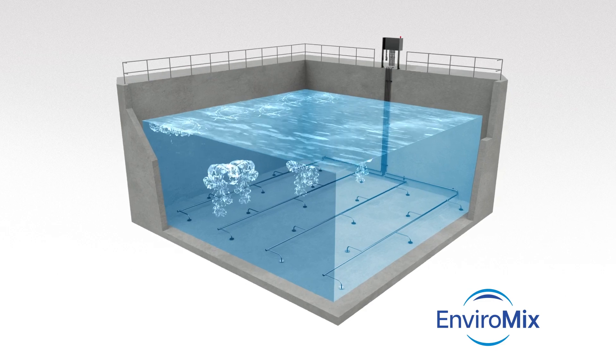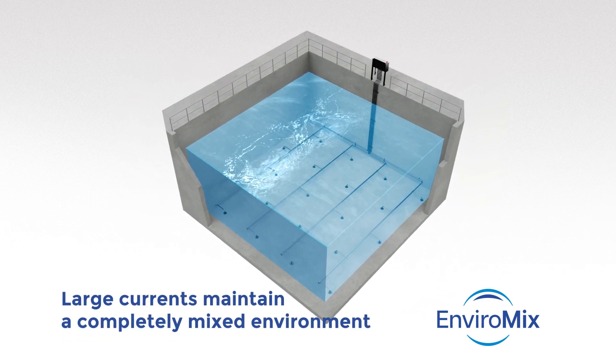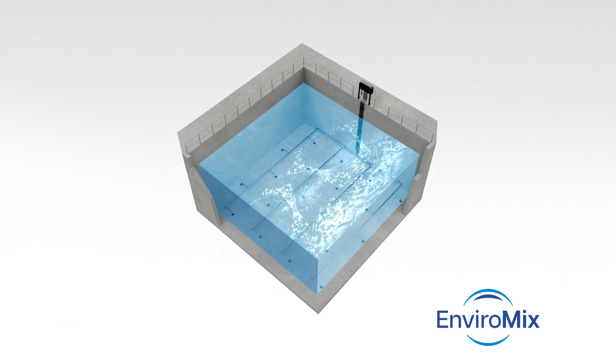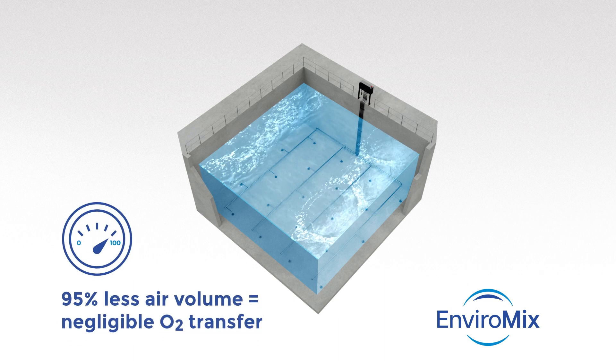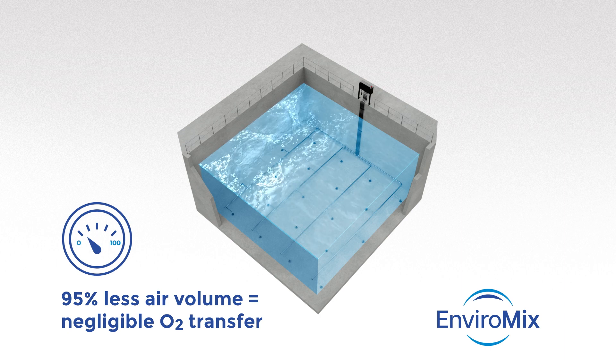On the surface, you can see the convergence of these currents and the uniform distribution of energy, showing the entire volume is mixed. And though it looks like coarse bubble aeration, EnviroMix produces a much larger intermittent bubble with 95% less air volume, so it doesn't transfer oxygen.